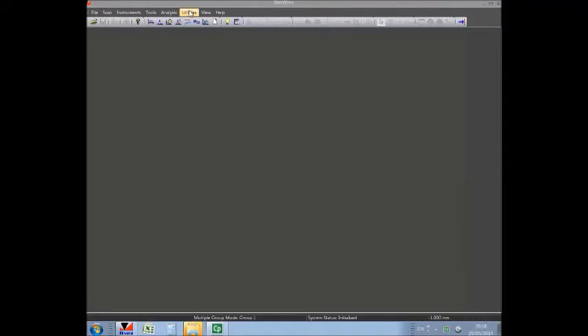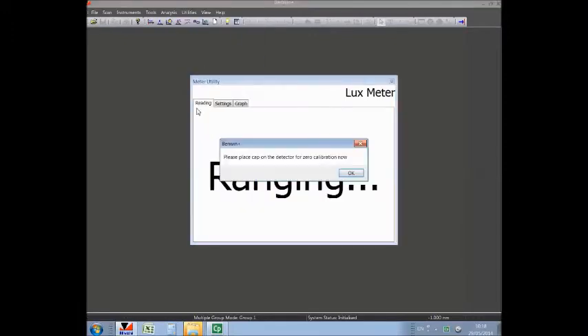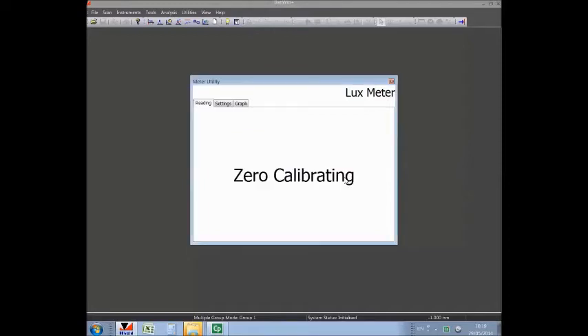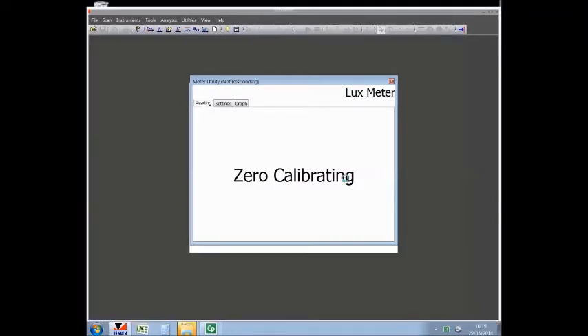In order to view the illuminance measured by the photometric detector, we go to Utilities, Meter. For the very first use, one should perform a dark measurement by ensuring the cap is placed in front of the photometric detector, hitting OK. And the dark current measurement will be performed and saved to file and will not need to be performed in the future.